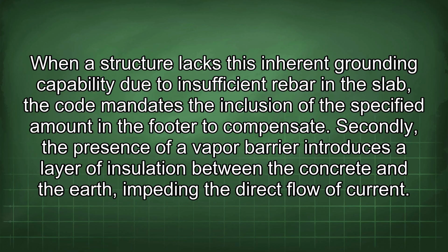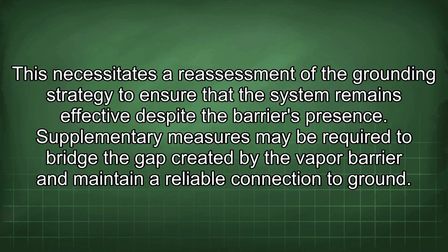Secondly, the presence of a vapor barrier introduces a layer of insulation between the concrete and the earth, impeding the direct flow of current. This necessitates a reassessment of the grounding strategy to ensure that the system remains effective despite the barrier's presence. Supplementary measures may be required to bridge the gap created by the vapor barrier and maintain a reliable connection to ground.